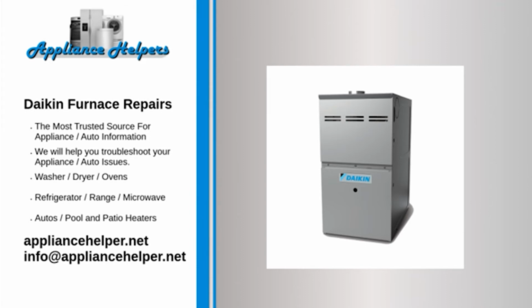The filter is dirty and must be replaced or cleaned, an issue that is especially true on newer furnaces that are equipped to shut down if the filter isn't allowing adequate airflow, a condition that can cause serious mechanical failure. The furnace's main circuit board: the control board is bad, an issue that can be diagnosed by an HVAC technician if nothing else solves the issue.